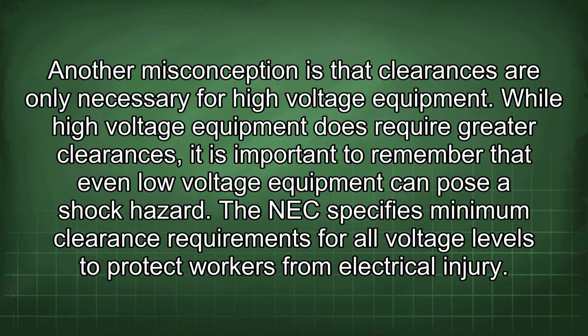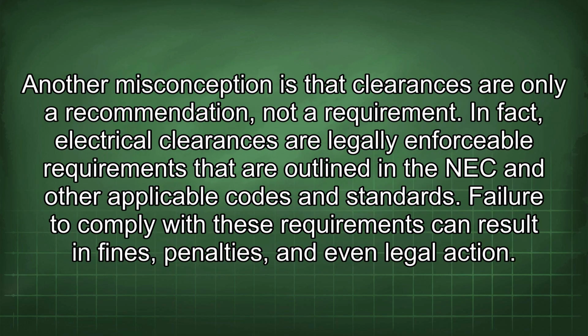Another misconception is that clearances are only necessary for high-voltage equipment. While high-voltage equipment does require greater clearances, it is important to remember that even low-voltage equipment can pose a shock hazard. The NEC specifies minimum clearance requirements for all voltage levels to protect workers from electrical injury. Another misconception is that clearances are only a recommendation, not a requirement. In fact, electrical clearances are legally enforceable requirements that are outlined in the NEC and other applicable codes and standards. Failure to comply with these requirements can result in fines, penalties, and even legal action.